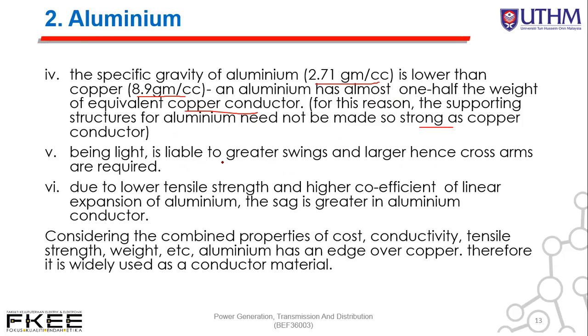So because it is light, the swing will be very great, easy to swing compared to copper. Hence larger cross arms are required. Due to lower tensile strength and higher coefficient of linear expansion of aluminum, the sag is greater in aluminum conductor. We will see the detail on the sag later in the chapter.